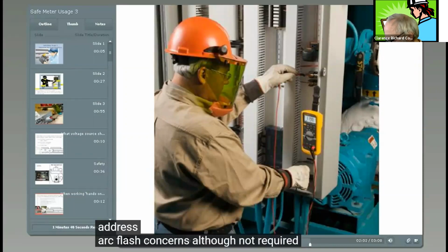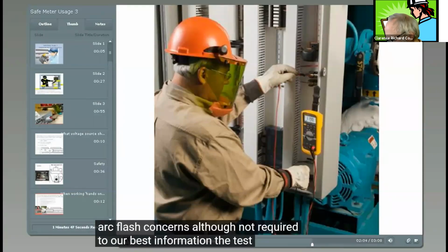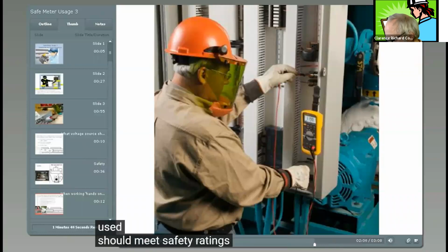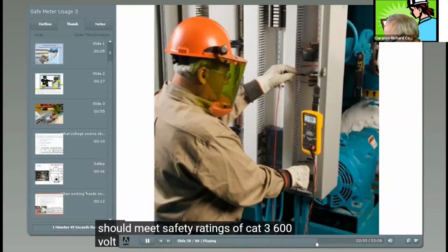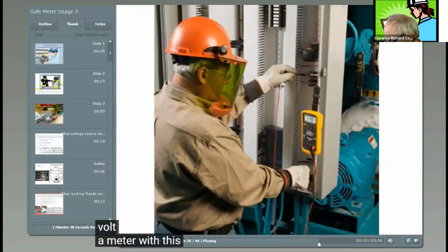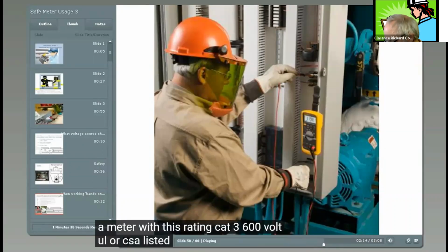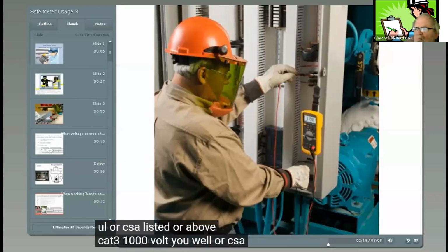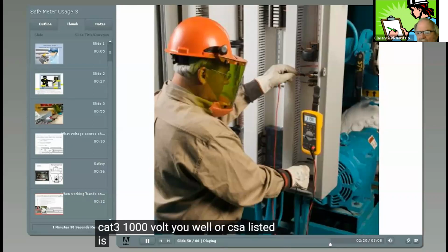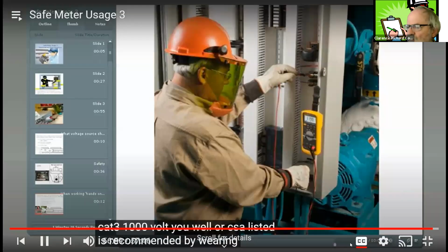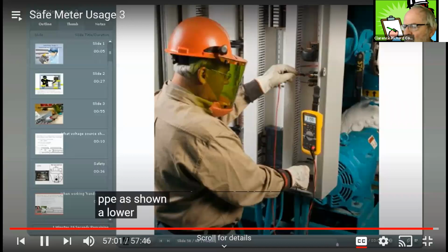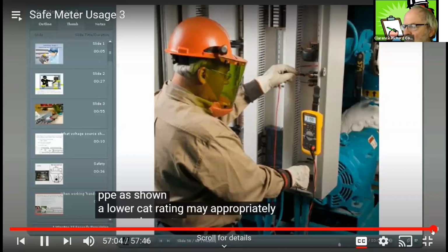Although not required, to our best information, the test meter used should meet safety ratings of Cat 3 600 volt. A meter with this rating, Cat 3 600 volt, UL or CSA listed, or above, Cat 3 1000 volt, UL or CSA listed, is recommended. By wearing appropriate PPE as shown, a lower Cat rating may appropriately protect the meter operator.